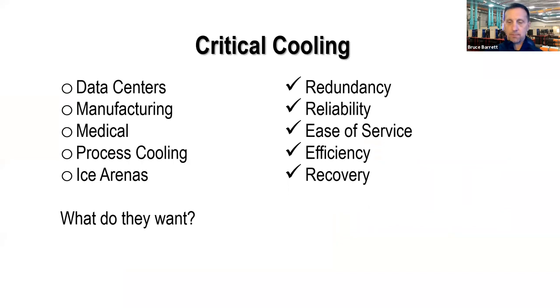Who might want these? Well, absolutely data centers come to mind at first, but also manufacturing with critical processes, medical and process cooling, ice arenas. If they have a failure, they need ice. They need backup. Again, all of those components of a modular chiller: built-in redundancy, added reliability even though a component may fail, ease of service. It may not be an emergency if a module goes down or a compressor goes down. Efficiency, let's not forget a modular chiller can be very efficient. And the recovery time.